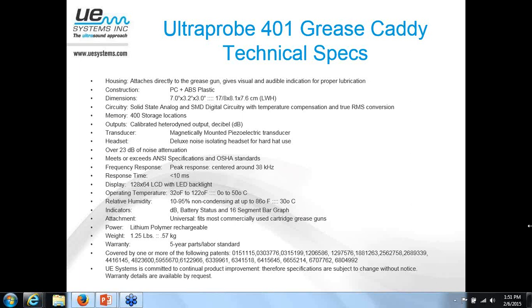Depending on how far away it is, if it were my facility, what I would do is install the RAS, the remote mounted sensors, which you can get on standard cable lengths of 25 feet or 50 feet. We can make them shorter than that, and we can make them longer than that. It's a stud-mounted sensor, so you run your cable back out, and then you've got your grease fitting coming out, and you would simply plug that RAS sensor directly into the Ultraprobe 401 and grease that way. That would probably be your best bet.